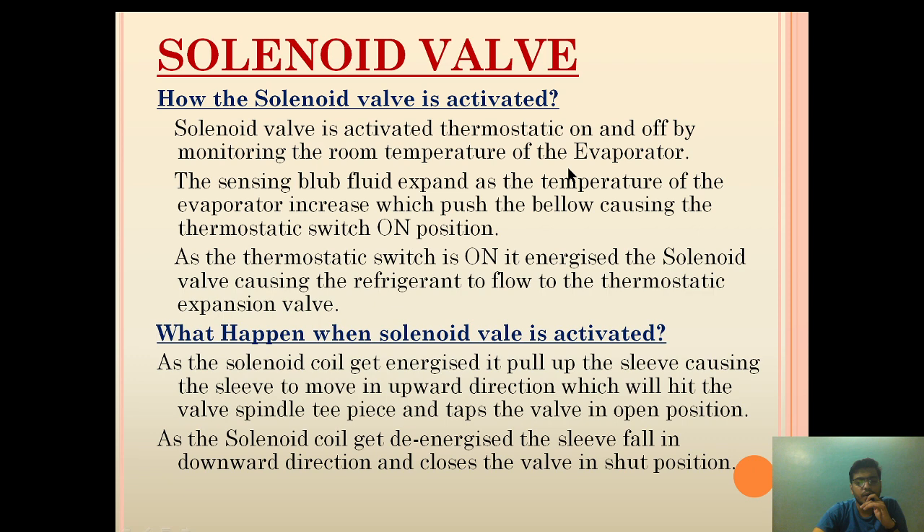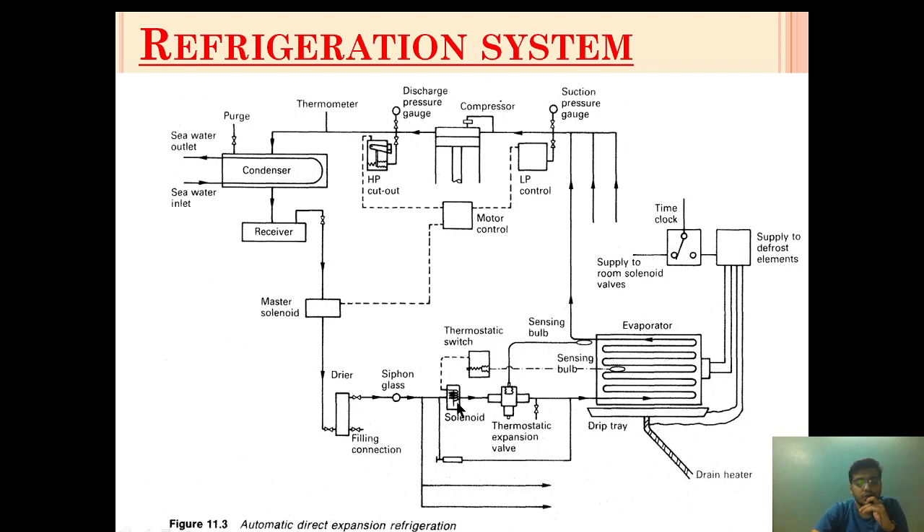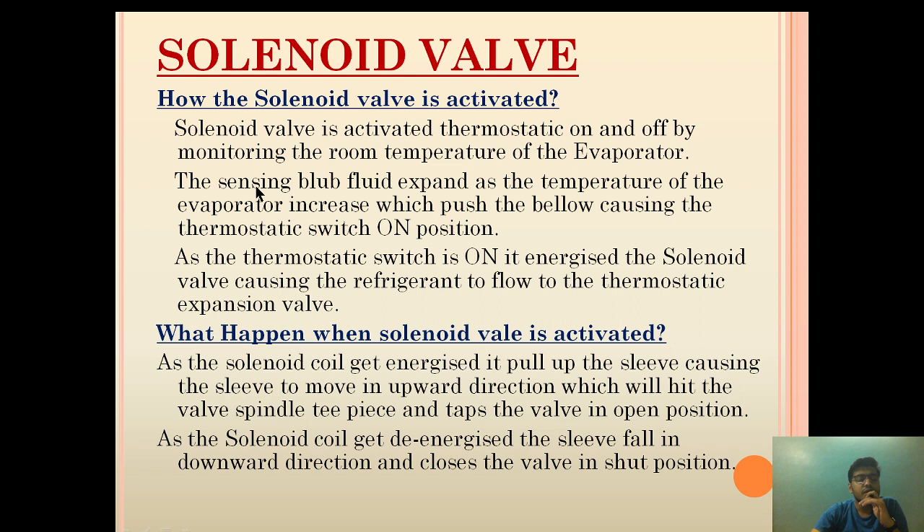How is the solenoid valve activated? The solenoid valve is activated thermostatically, on and off, by monitoring the room temperature of the evaporator. The thermostatic expansion valve allows the flow of high-pressurized refrigerant, controlled by a thermostatic switch. This thermostatic switch gives an electrical signal to the solenoid valve to activate it and allow the refrigerant to flow. This electrical switch is activated by the sensing bulb provided inside the evaporator.